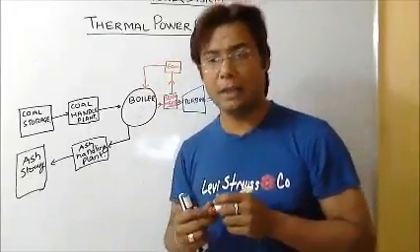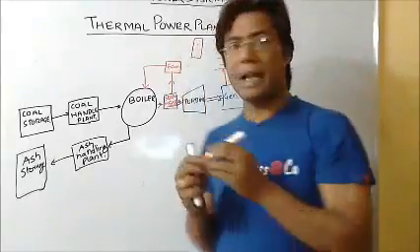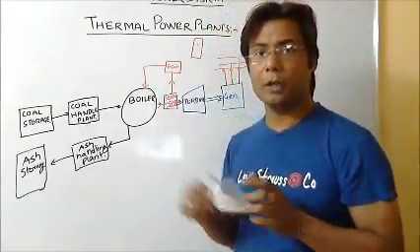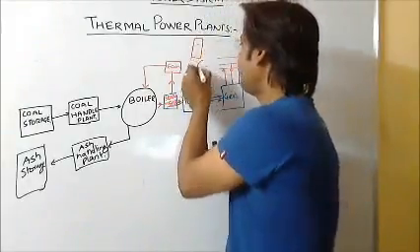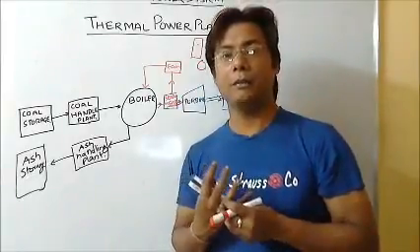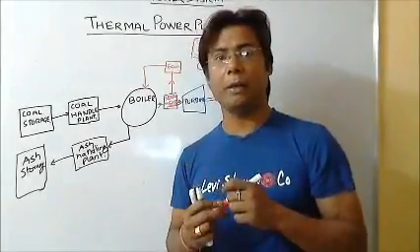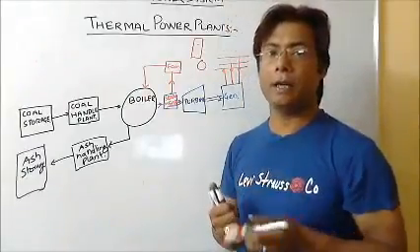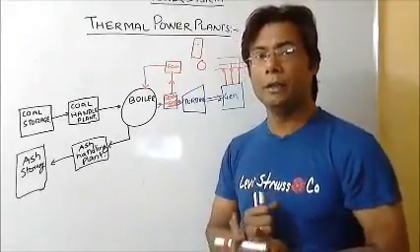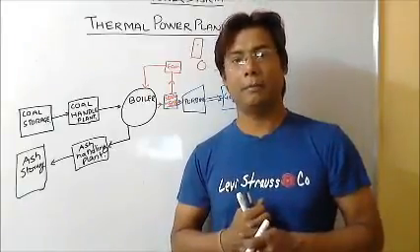My flue gases will be there, and a flue gas chimney will be there. A chimney will be connected here, and the gas flowing out of the boiler can again be used, since there can be a fan before the chimney which will take the heat from the chimney, so that the heat which is flowing away into the environment can be used again to boil the water. And it is said that every 10 degree increase in the temperature of the water will increase the efficiency of the plant by 1%.